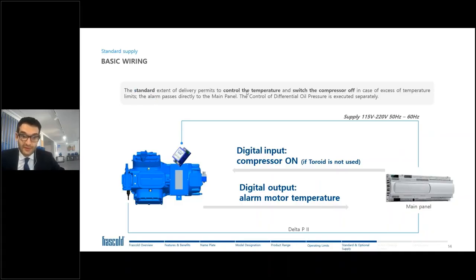So here is the standard extent of delivery that allows you to connect it with the big majority of controllers already present on the market. The delta P2 must be connected to the main panel and gives you an alarm in case of a problem with the oil pump. Instead, the control injection card gives you an alarm in case of high temperature and needs an input to understand if the compressor is on or off. As standard, we also supply a toroid that is very simple to put on the power supply cable of the compressor, and you can use this toroid to give the compressor on or off signal to the device. Otherwise, if the toroid is not used, you can give this device a simple on-off signal. This is our standard, this is the basic wiring.